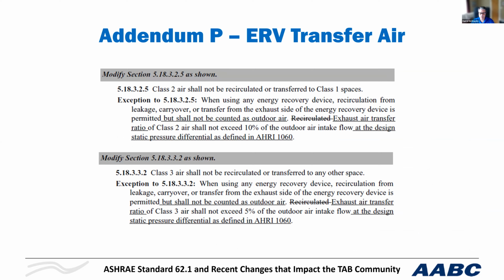And one important thing about energy recovery is, there is always a little bit of leakage. It's called exhaust air transfer ratio. And the allowance for this leakage has been around for quite a while, a few versions of this standard. However, there's a new clarification in this addendum that this leakage now does not count as ventilation air because it is tainted air. Thereby, when you're balancing, your balance better be on the high side on the total outside airflow, because you can't count that 10%. So you don't want to be balancing exactly with respect to that.